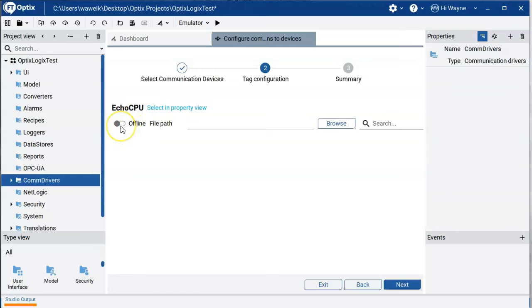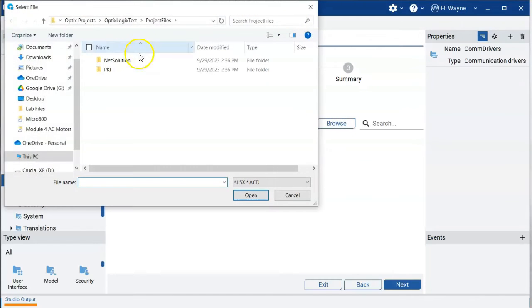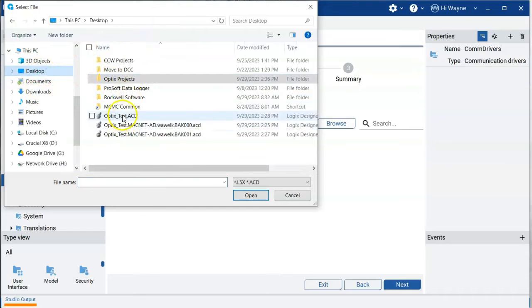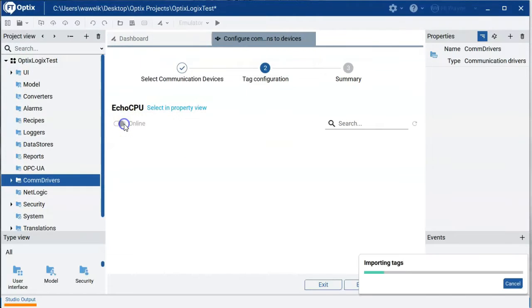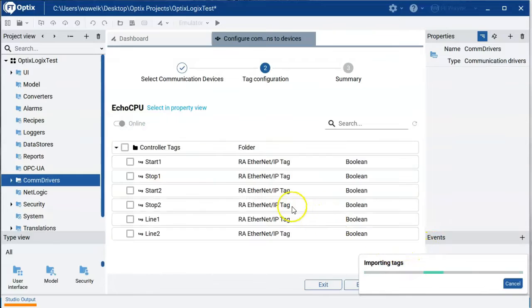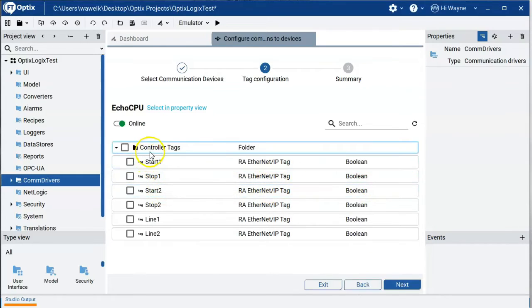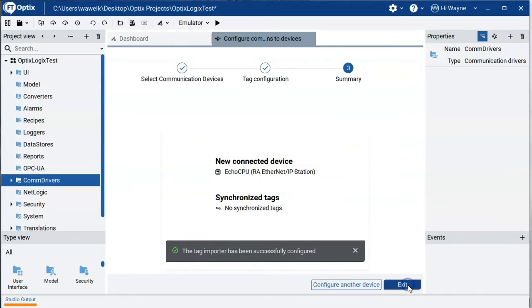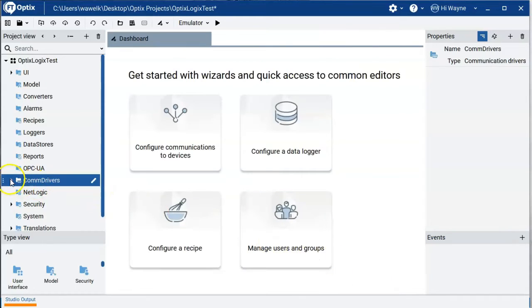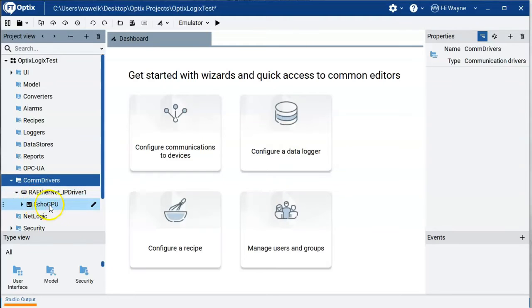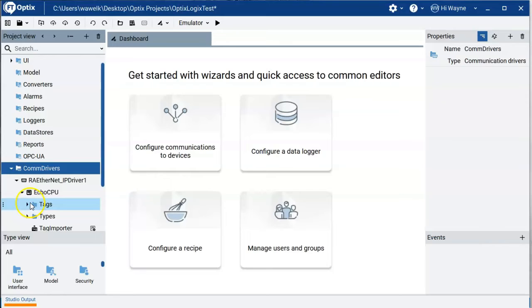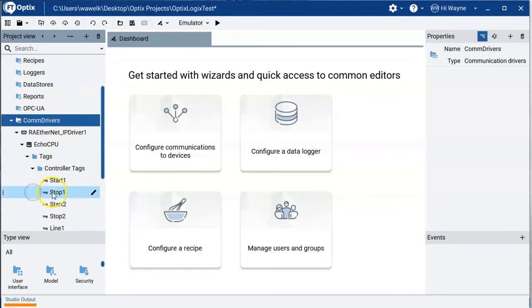After naming the station, I have the choice of browsing for tags either offline or online. Offline lets me browse to my ACD file on the desktop and it'll find the tags. Online will import the tags directly from the live controller. Since I'm using the emulator, it sees the live controller and all its tags. Now you can see the RA Ethernet/IP Driver with our Echo CPU device and the controller tags we just imported.